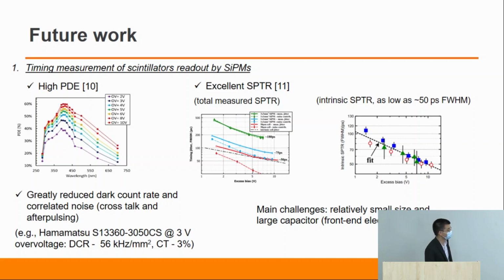For this 3 by 3 millimeters silicon photomultiplier, we could get a single photon time resolution of about 180 picoseconds. This is very close to the transit time spread of the first PMT, which is 160 picoseconds.